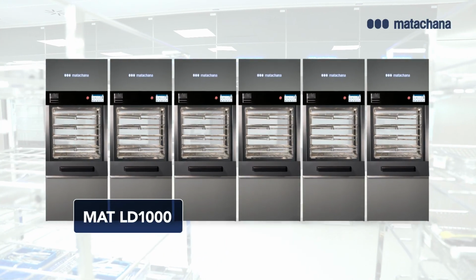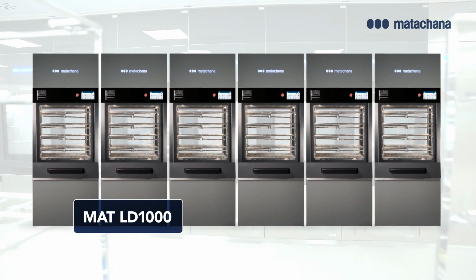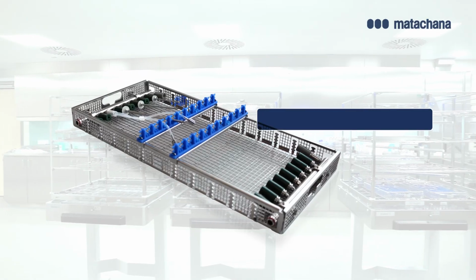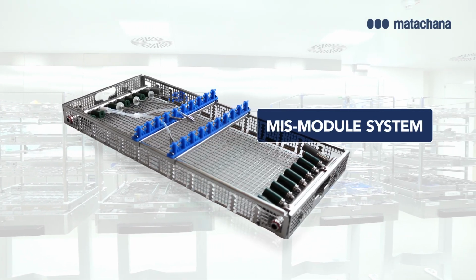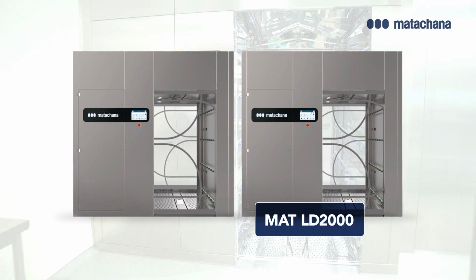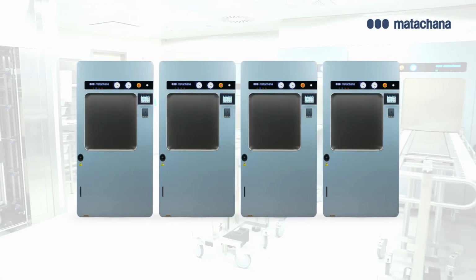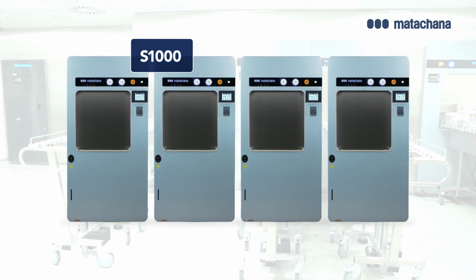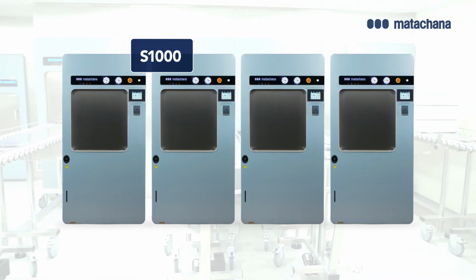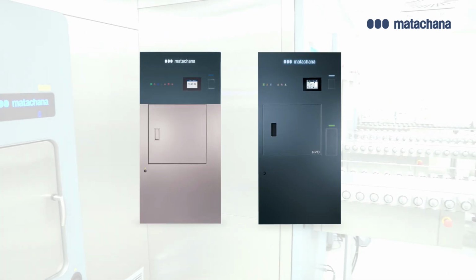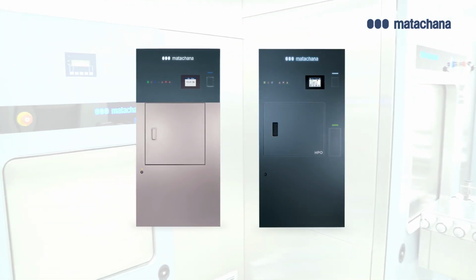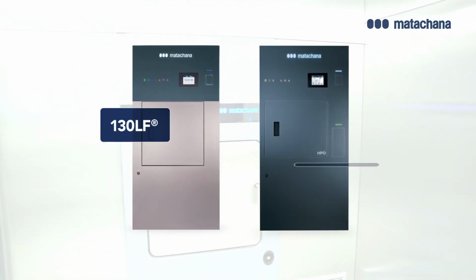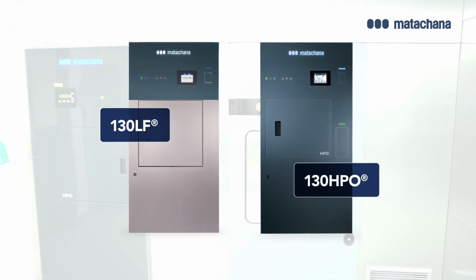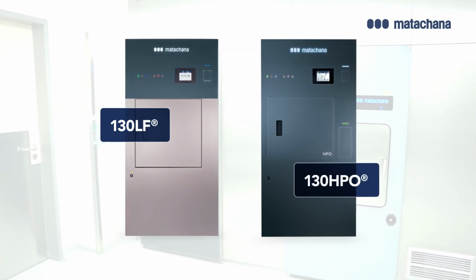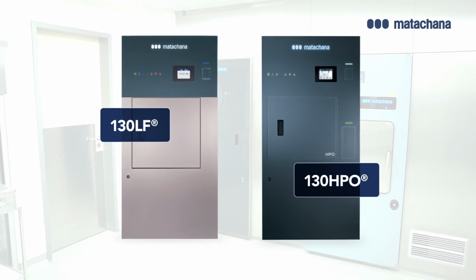A first line of 6 washers thermodisinfectors for 18 baskets, including our MIS module system, and 2 washing and thermodisinfection cabins for containers. The sterilization range includes 4 steam sterilizers for 8 baskets with automatic unloading and 2 low-temperature sterilizers, one operating with formaldehyde and the other with hydrogen peroxide, to cover all the needs with regard to the sterilization of heat-sensitive material.